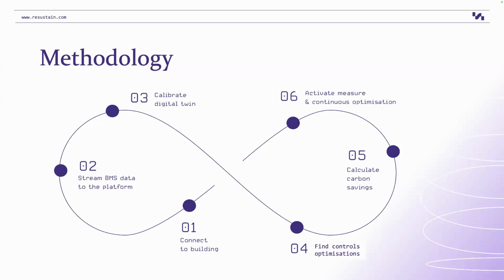The methodology for this case study was to connect into the BMS, stream that BMS data onto a platform, translate it, and create a calibrated digital twin using BMS data and utility bills, then find the control optimizations. We run those optimizations through the digital twin, the calibrated model, to forecast what savings might be possible, and then start activating the measures and realigning the building according to the optimizations we find.